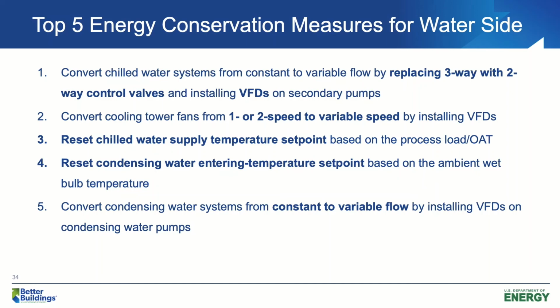Water side. Convert your chilled water system from constant flow to variable flow by replacing 3-way control valves with 2-way control valves and installing VFDs on your secondary pumps. Change all your cooling tower fans from 1-speed or 2-speed controls to VFD controls. Reset chilled water supply temperature based on the process load or outdoor air temperature. Reset condensing water temperature based on outdoor air wet bulb temperature. Convert your condensing water system from constant flow to variable flow.